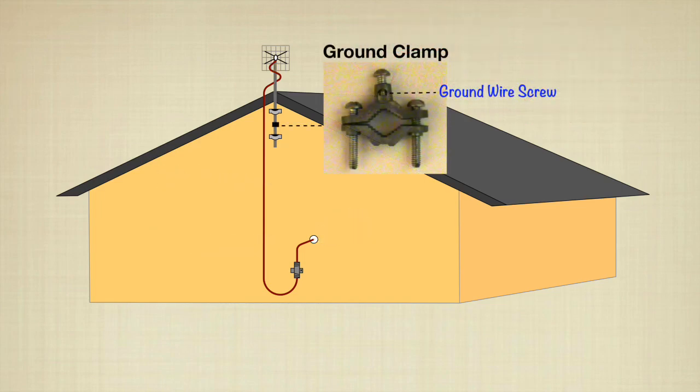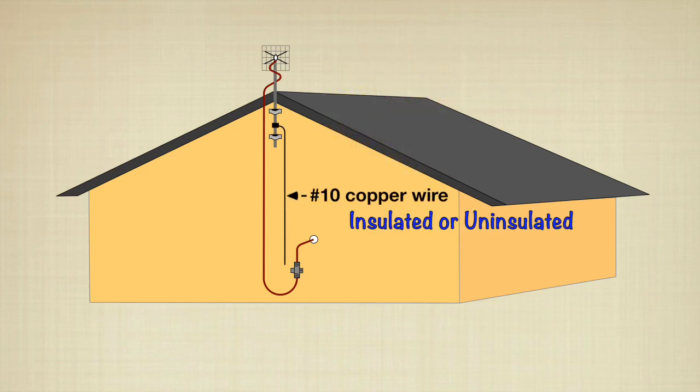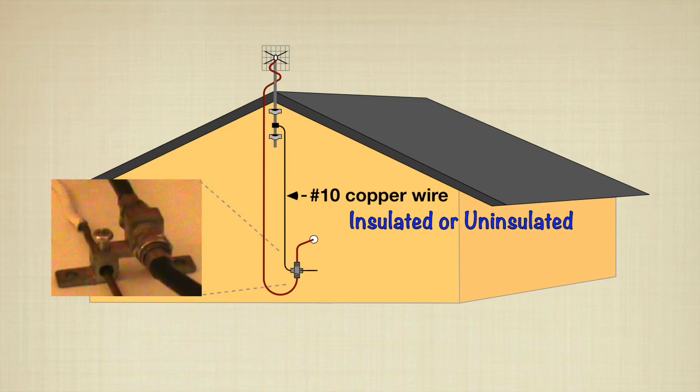Next, attach a ground clamp to the antenna mast. Connect number 10 copper wire to the clamp. It can be insulated or uninsulated. Then run the wire through the coax ground block, making sure the bare copper makes good contact with the block screw.